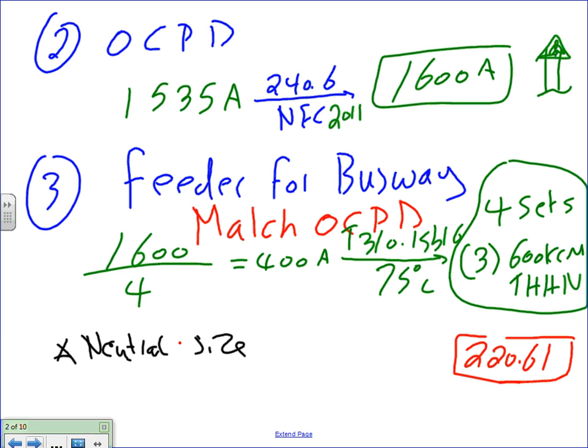I could have paralleled, if you know, Chris, if you paralleled five of them and you end up with five sets, it doesn't hurt my feelings. The rule when we parallel, guys, is you want to parallel the least amount of sets and still hover around 500 kcmil. That's kind of the rule of thumb. The least amount of runs is the best. But you also don't want to do two of them and end up with something like 2000 kcmil cable. That will be so hard to find a conduit that fits them and pull them. So the rule of thumb is the least amount of conduit runs and hover around 500 kcmil. 500, 600 is pushing it a little bit, but even lower than that. Okay.